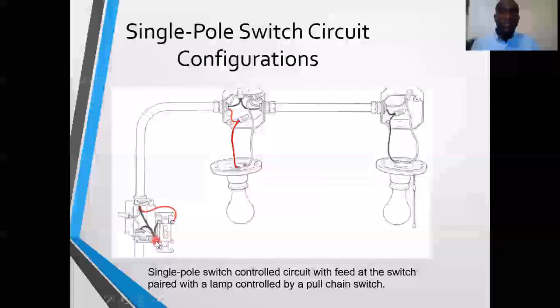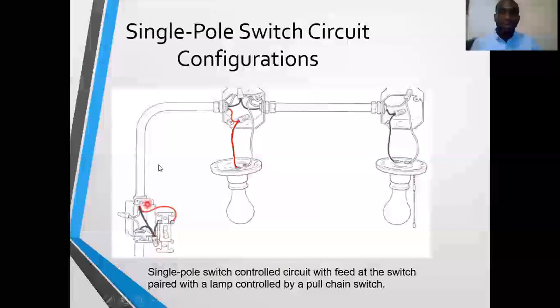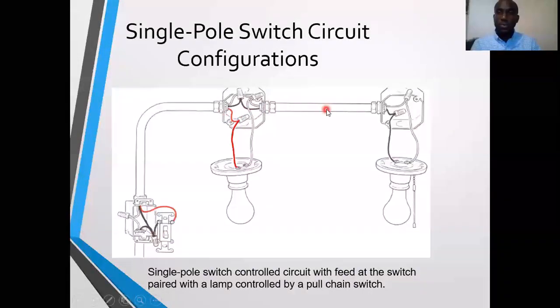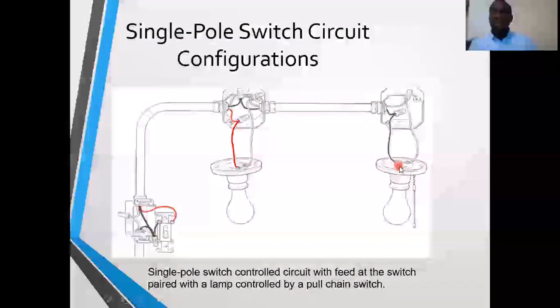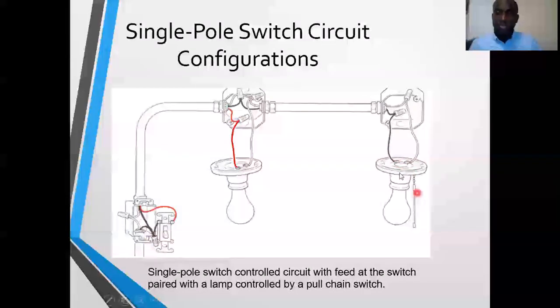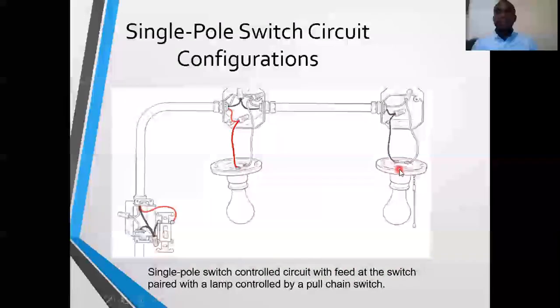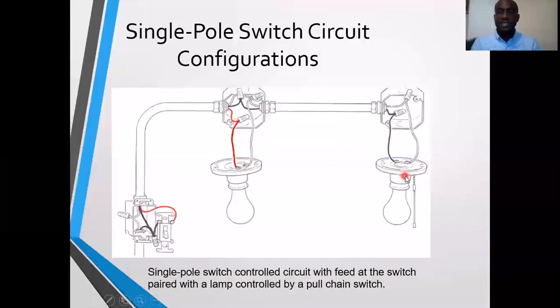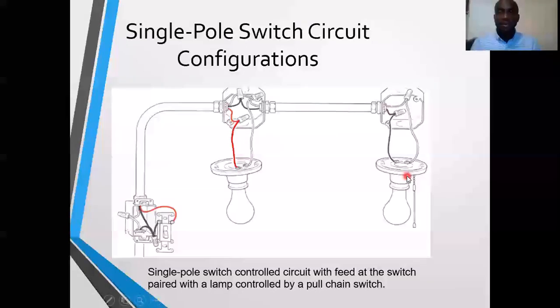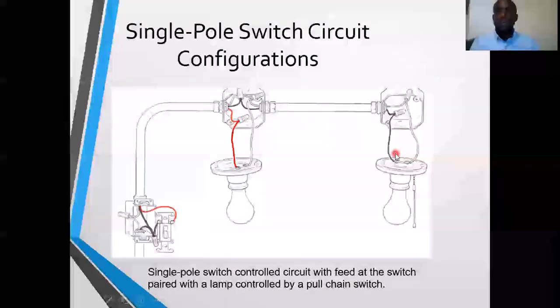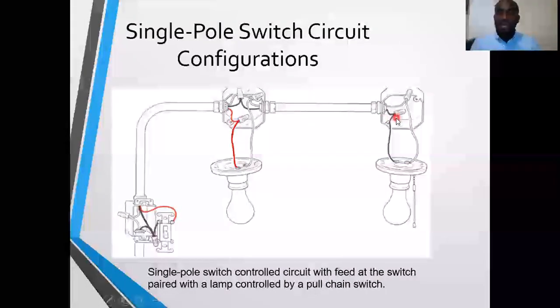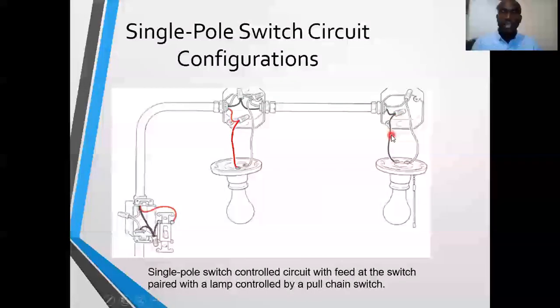Now this hot that we would have shared at the beginning, we send it all the way through and connect it to the brass terminal of the lamp that is serviced by the pull chain switch. It is very important for you to understand that when a lamp or device has its switch attached directly to it, you will send a black directly to it and not a switch feed red.